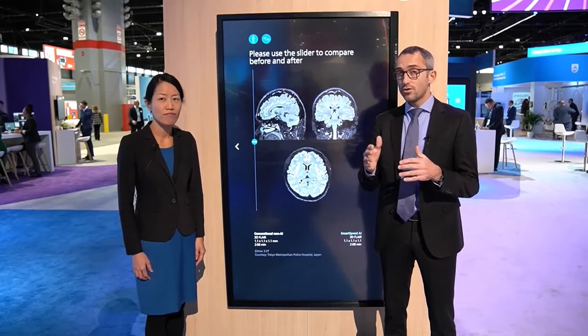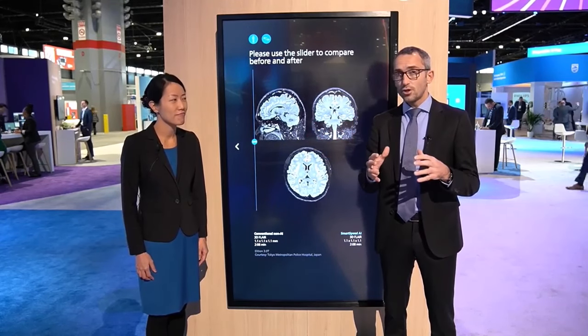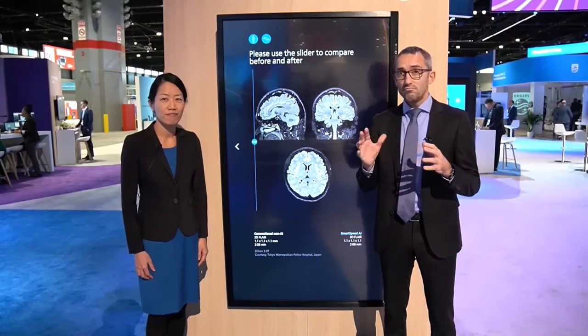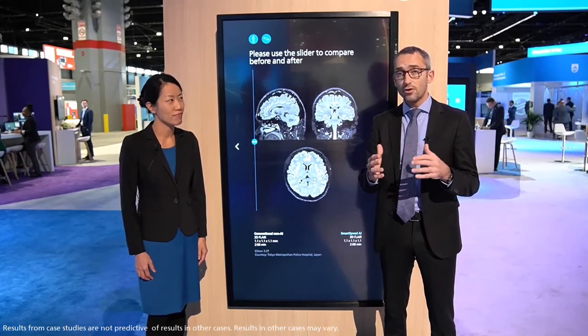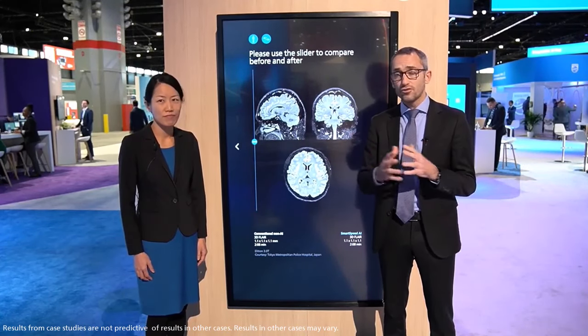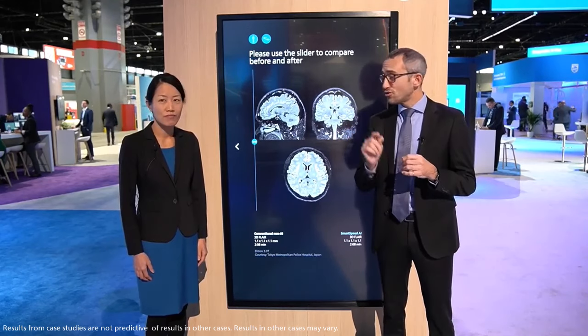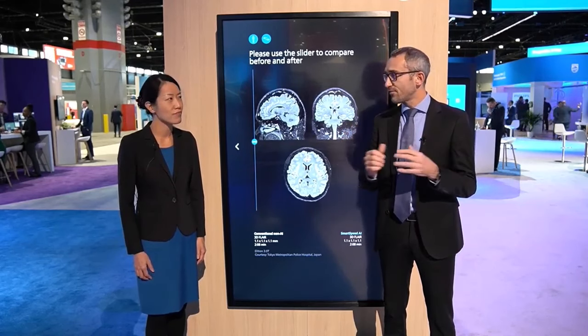Especially on the 7700 system, we are showing increased image quality with 3D scans in below three minutes and isotropic resolution of one millimeter or below — for FLAIR, for T1, for time of flight, for SWI. This is the strength of SmartSpeed: it is applicable to so many sequences in practice.